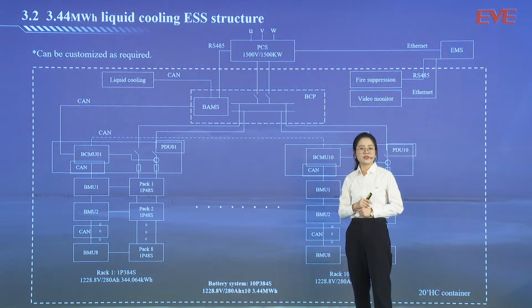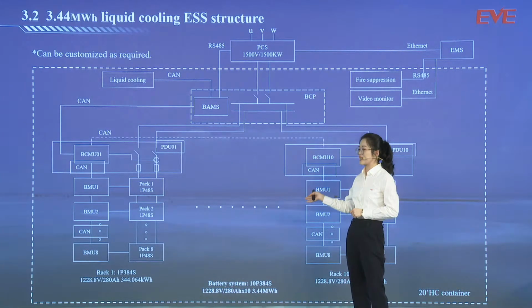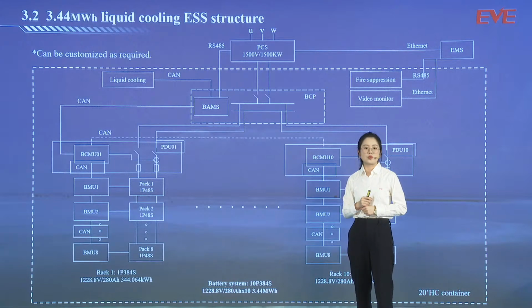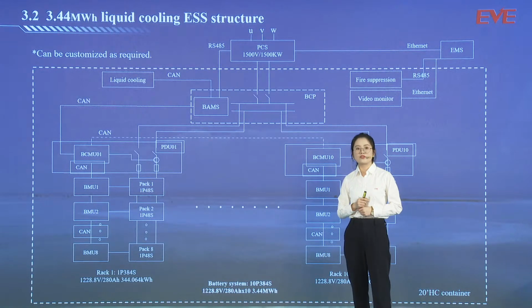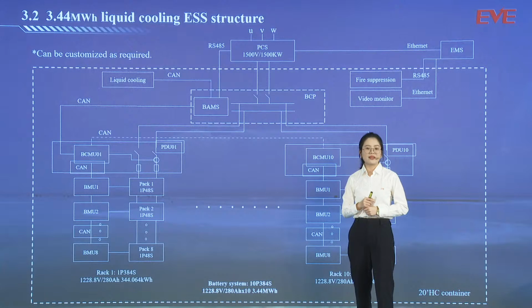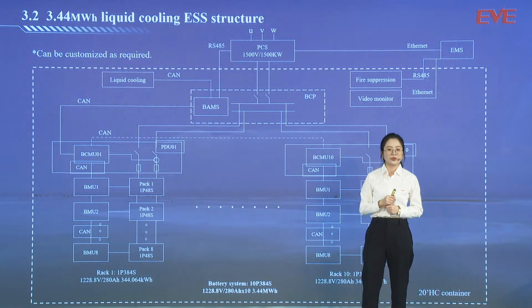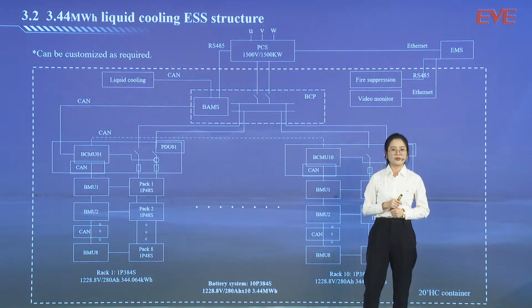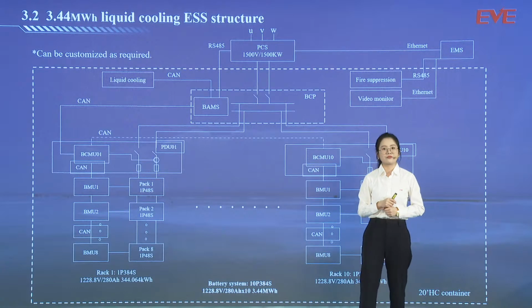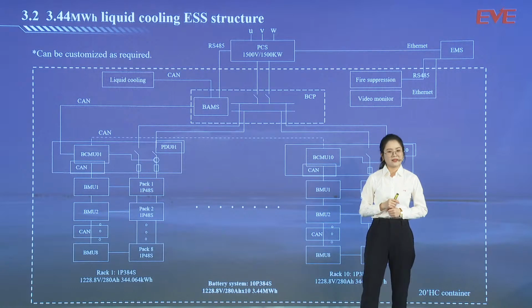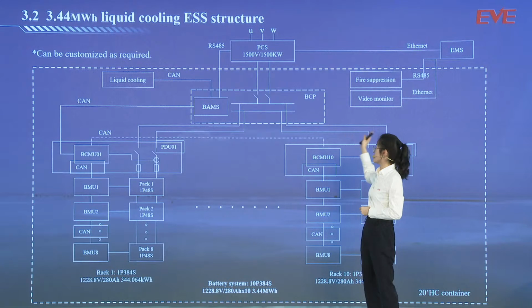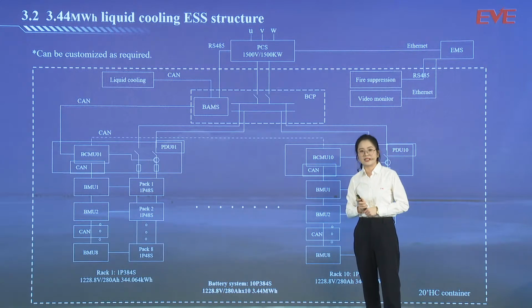The entire 3.44 megawatt-hour liquid cooling system is designed with 8 battery packs connected in series to form a battery rack, for a total of 10 battery racks, with a 3-level BMS architecture. BMS communicates with the liquid cooling machine and battery through the CAN protocol, and mainly communicates with PCS through RS485 according to the PCS protocol. The protocol between PCS and EMS is Ethernet.